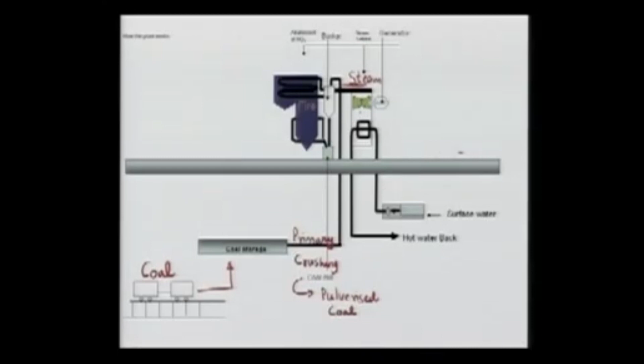How the condenser really works, because this also has environmental issues: you take the surface water, or it could be water from the sea. Suppose there is a river here, and you are pumping the water and providing a large surface area. This cool surface water comes in contact, not the water but the surface, which comes into contact with the steam, and the steam as a result will condense, okay, and make water here. This cooling water is in a closed circuit here. It doesn't come in contact with the steam, and is taken out and disposed of back to wherever the source was.